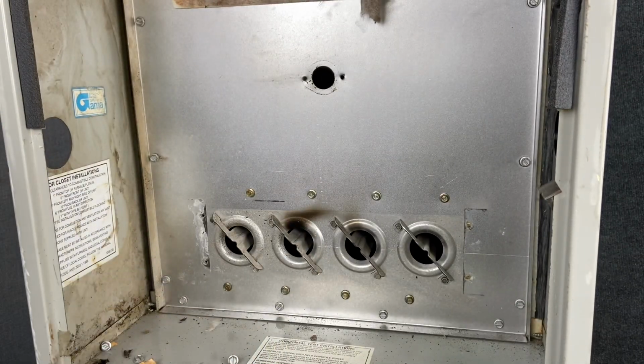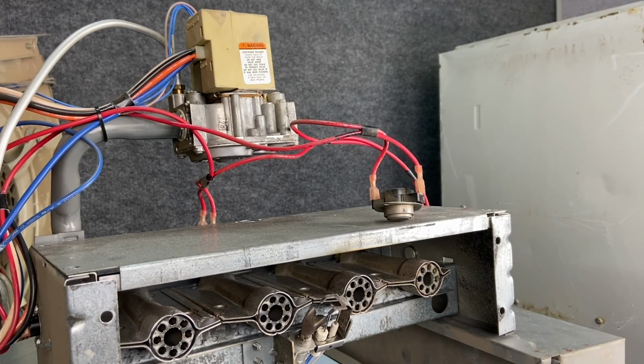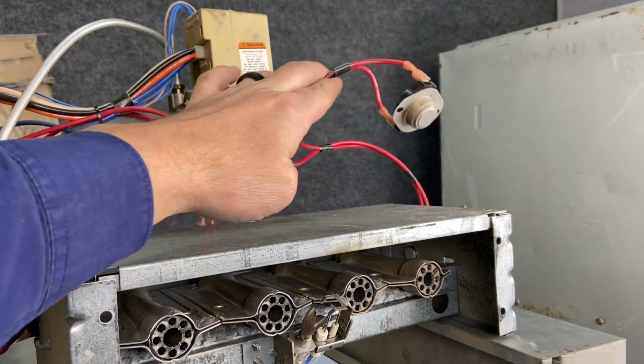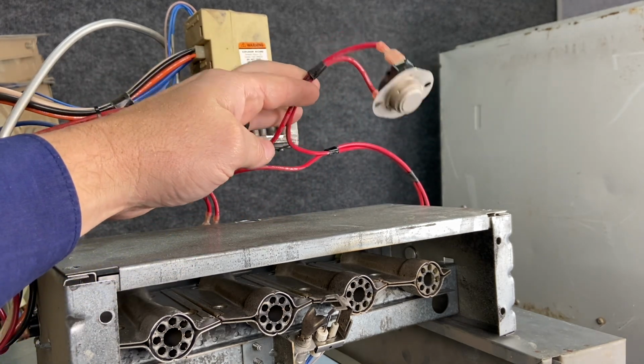Let me rearrange this so we can get a better view of it. So here we have our burners pulled out from the gas furnace so we can see everything. Now what you're looking at is the side that faces the furnace, the side that faces the heat exchanger. So now we can get a good look at everything. Here we have our main limit switch. This is going to be what's sensing for the air.